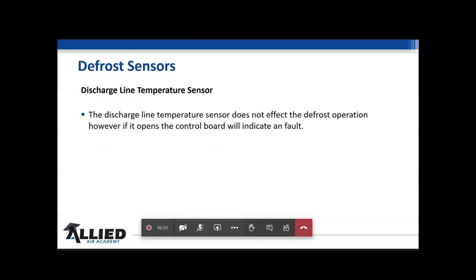And as I said, the discharge line temperature sensor is kind of a nice backup to the high pressure switch. So if that line gets too hot, for some reason or another, if the high pressure switch is messed up, then it'll take it out, but it's not going to affect any way the defrost is going to work. So if anybody asks, does that have an effect? No, it does not.